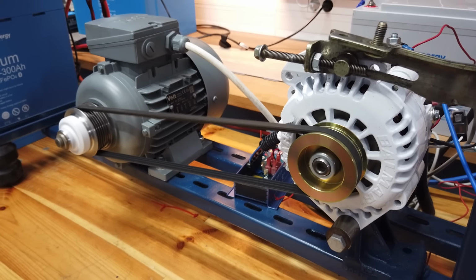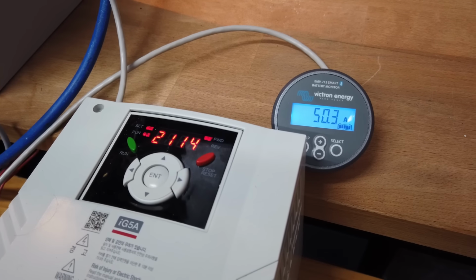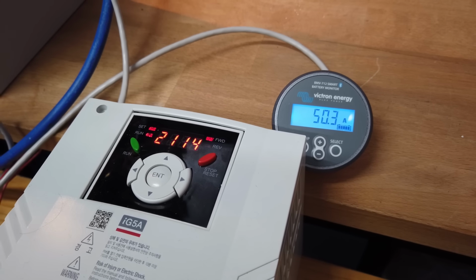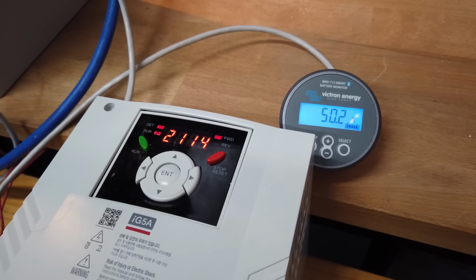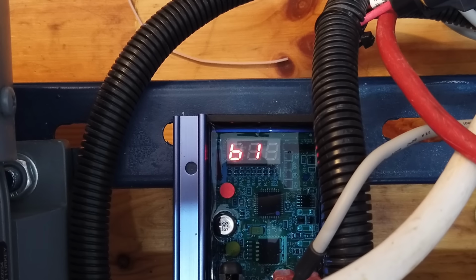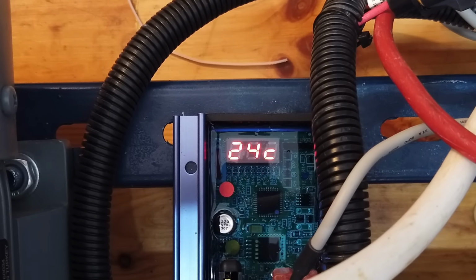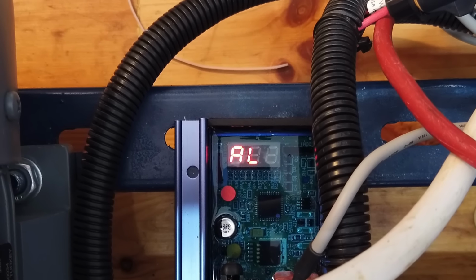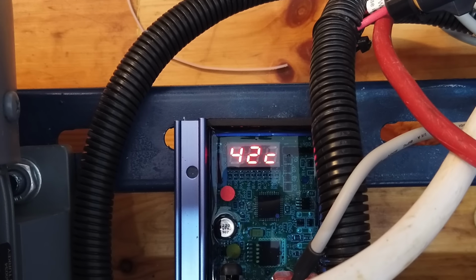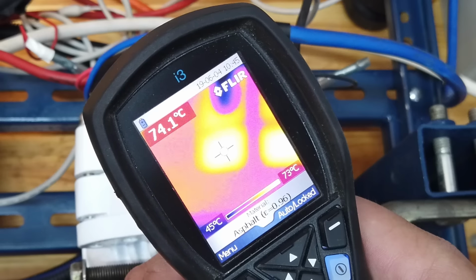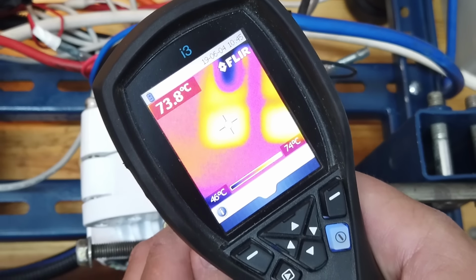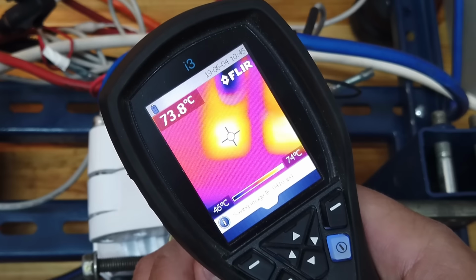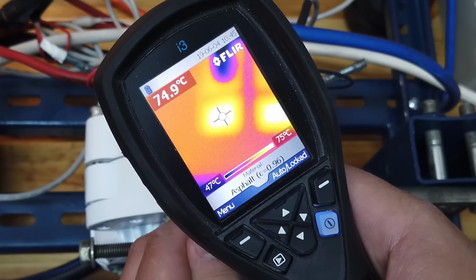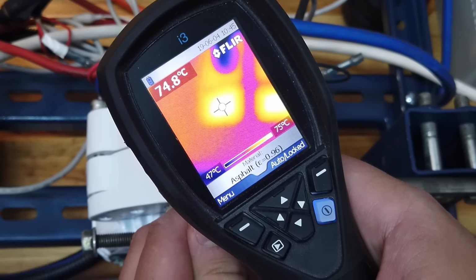Our initial test was at 2114 RPM. This produced a steady 50 amps. The regulator indicated an ambient temperature of 24 Celsius and 42 Celsius for the external casing of the alternator. We used a temperature monitor, and you can see at the top left of the device the alternator's internal temperature is around 74 degrees Celsius.